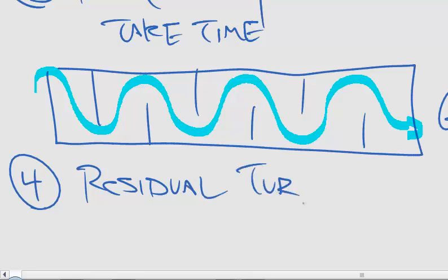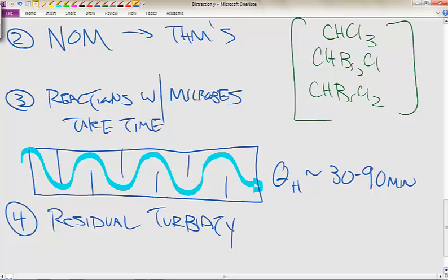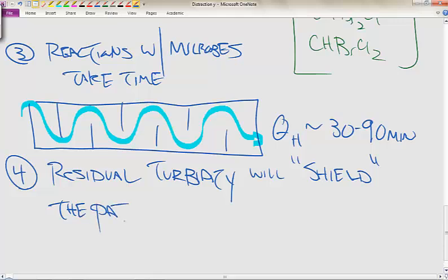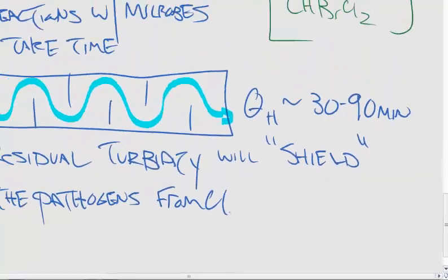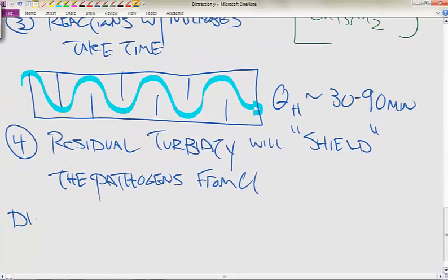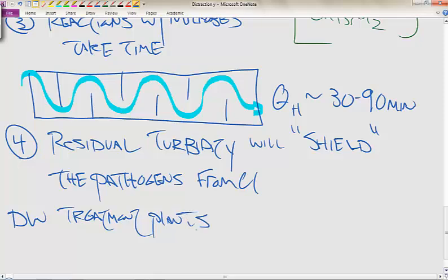Number four here is the residual turbidity. Residual turbidity that you have in the water will or may shield the pathogens from chlorine. If you have some dirty water, the chlorine might not see or react with those pathogens that you have there, and it's not going to be as effective. So you must really have clean water to disinfect.